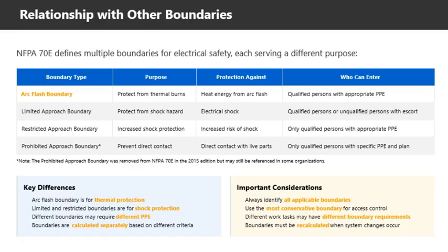Let's look at this comparison table. The arc flash boundary, which we've been discussing, protects against thermal burns from heat energy and allows entry only by qualified persons with appropriate PPE. The limited approach boundary protects against shock hazards from electrical contact. Qualified persons can enter this boundary, and unqualified persons can enter with a qualified escort. The restricted approach boundary provides increased protection against shock hazards where there's an increased risk of electrical contact. Only qualified persons with appropriate PPE can enter this boundary. There used to be a prohibited approach boundary that prevented direct contact with live parts, but this was removed from NFPA 70E in the 2015 edition, though some organizations may still reference it.